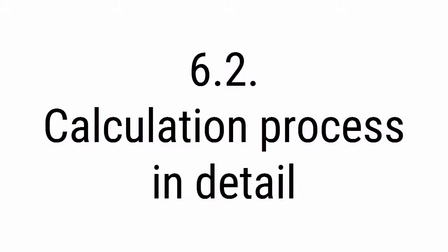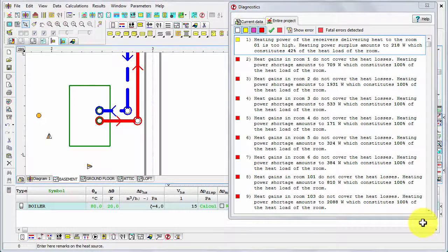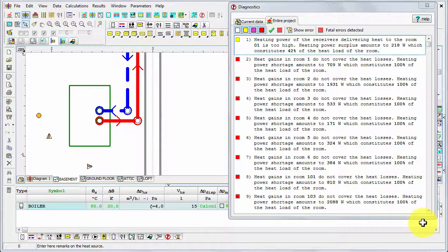So, now let me tell you about calculation process a little bit more in detail. Some kind of secret information, just for your knowledge. Of course, I'm kidding. Now, there are three main phases of the calculation process. The first one is checking the data. The program checks whether data is OK, complete, and if everything is OK. Then the program goes to the second step, which is the real calculations. Calculation of flows, selecting the diameters of pipes, selecting radiator sizes, and so on and so on, depending on the scope of calculations that you have selected in the global data.